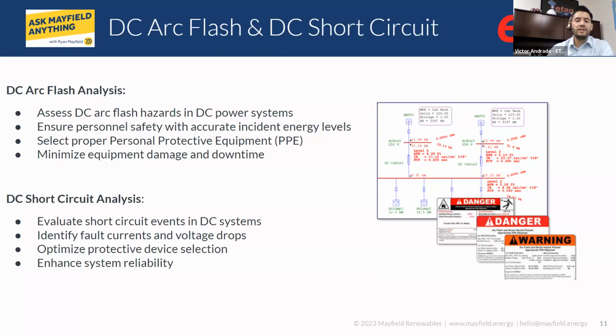And an arc flash essentially is a very quick release of large amounts of energy, almost like a fire, an explosion, an electrical explosion. So the labels are important because before the qualified electrician opens the equipment to do any kind of work live, they see the label. The label will say, warning, you must wear this PPE.